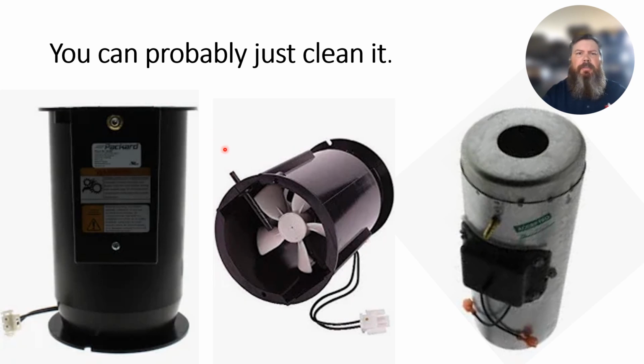They do seize up. So you can either run and go get a part and come back at a different time, or I've had a lot of luck using a non-conductive electric motor cleaner spray. Pull these units off, spray the motor, get the fan going, spray it again, keep turning it, and it will eventually loosen up for you. You can get that motor good and cleaned.